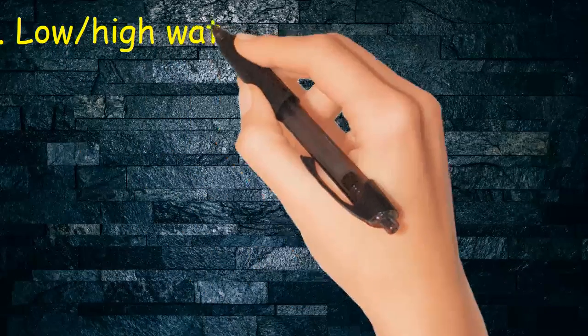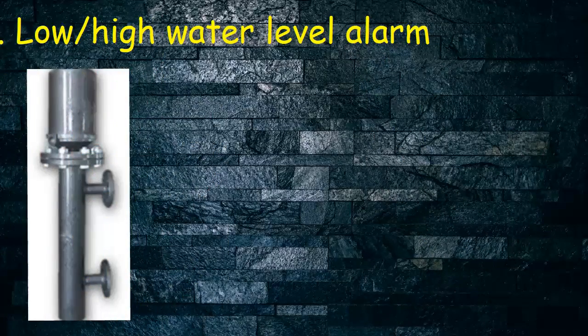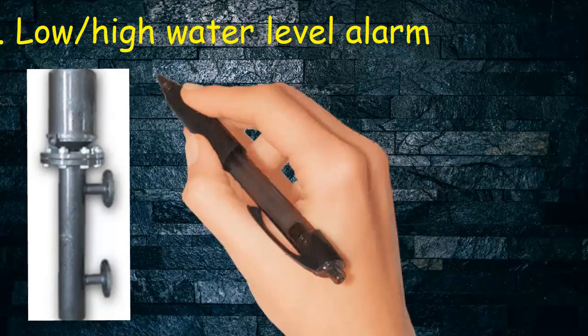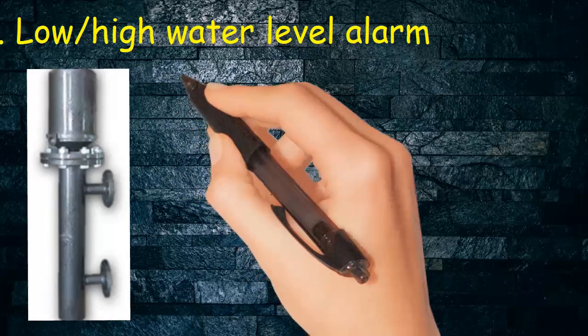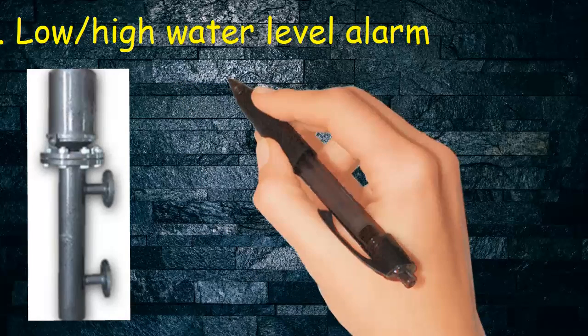Low high water level alarm. The boiler drum is fitted with water level indicator which constantly monitors boiler water level. A full drum will carry over the water or will have no space to generate steam, thus reducing the efficiency of the boiler.